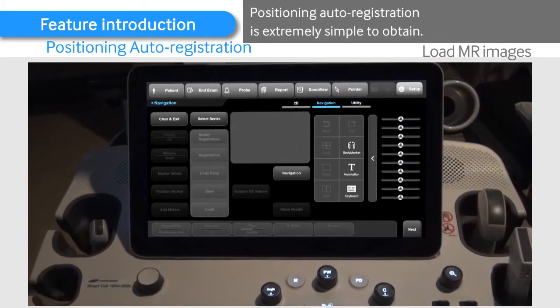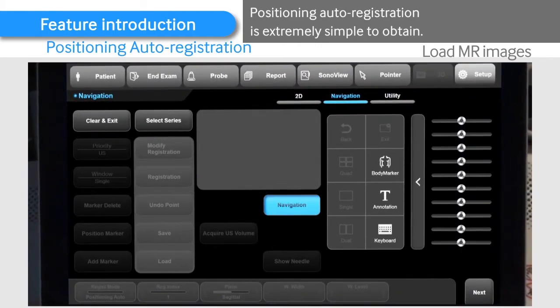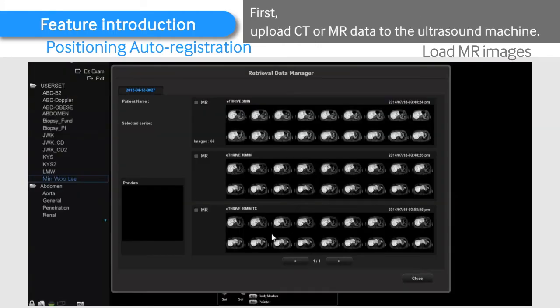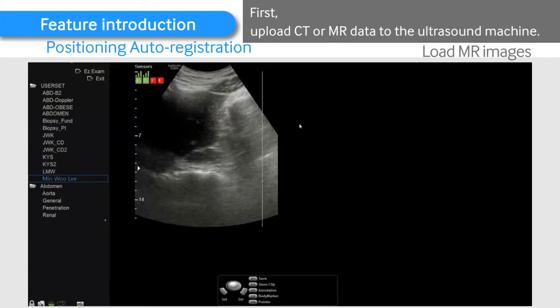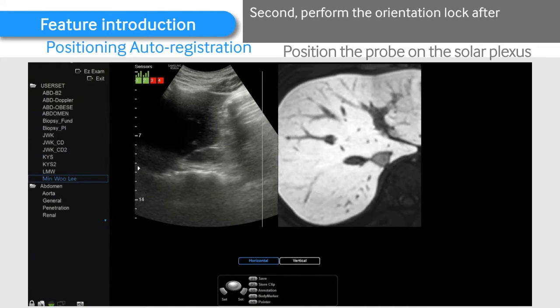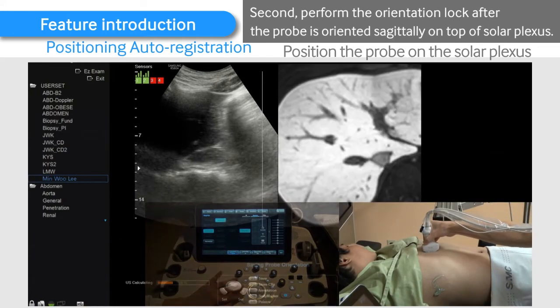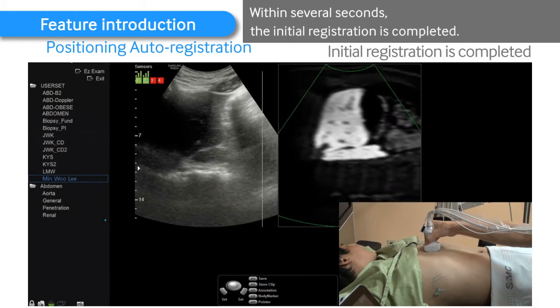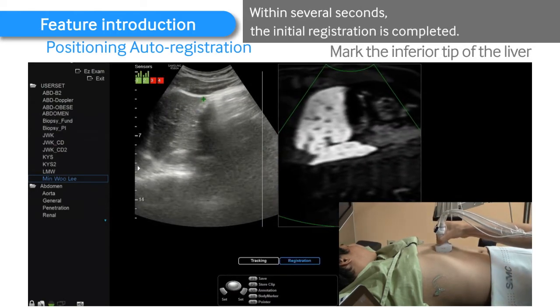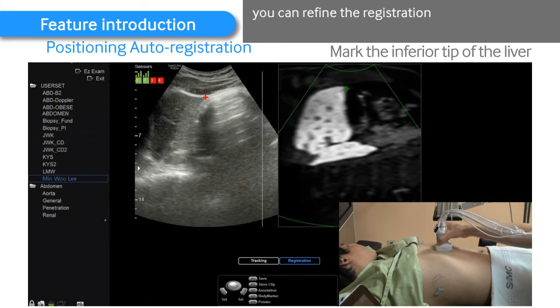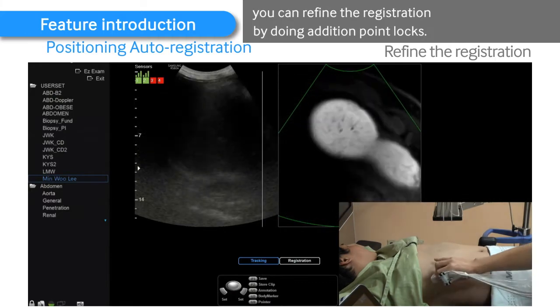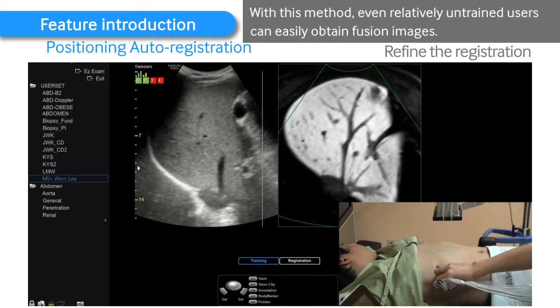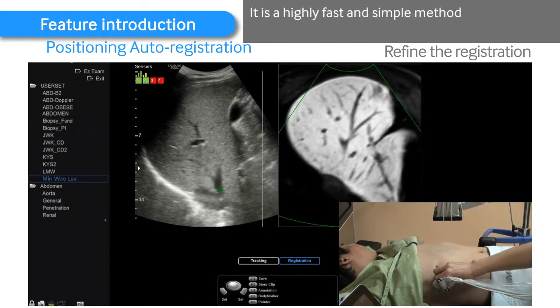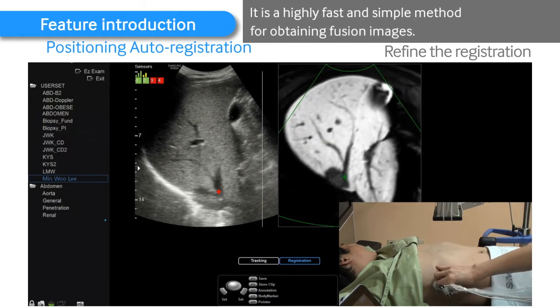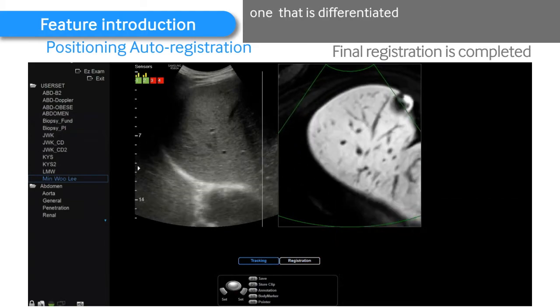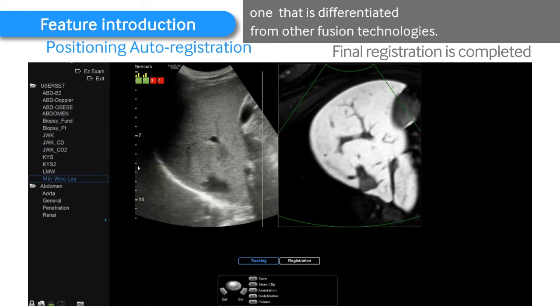Positioning auto-registration is extremely simple to obtain. First, upload CT or MR data to the ultrasound machine. Second, perform the orientation lock after the probe is oriented sagittally on top of the solar plexus. Within several seconds, the initial registration is completed. After the initial registration is completed, you can refine the registration by doing additional point locks. With this method, even relatively untrained users can easily obtain fusion images. It is a highly fast and simple method for obtaining fusion images. This method is unique to S-Fusion, one that is differentiated from other fusion technologies.